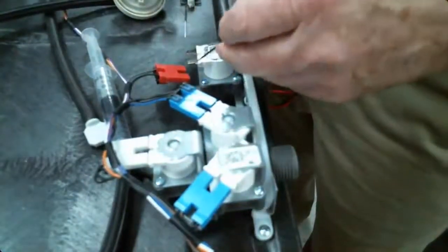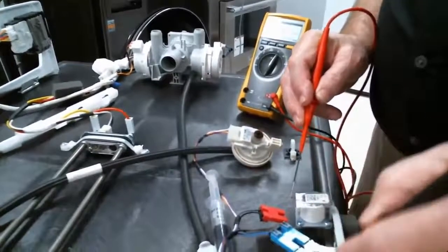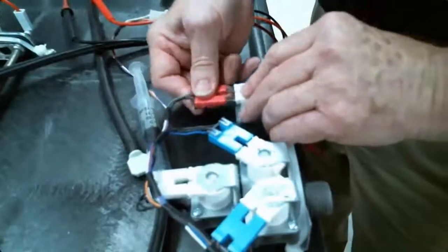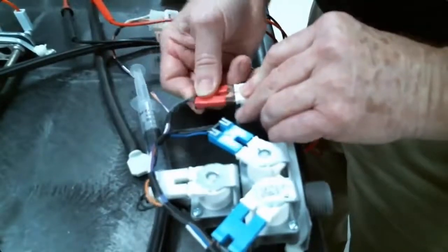Or of course, you can do resistance checks on these. You can also do voltage checks, and you can do it at the board. I'm getting approximately 26.2 ohms, and it's going to be identical readings for all of these valves. These are color coded. Red is going to be a separate valve.